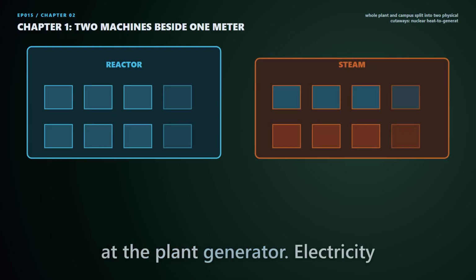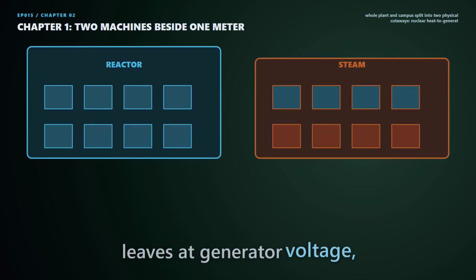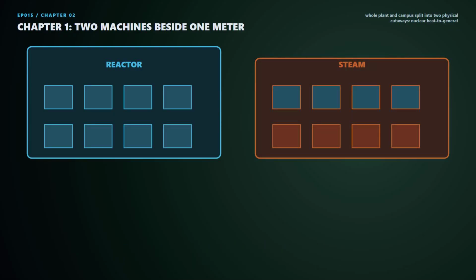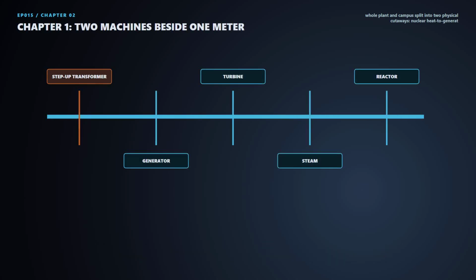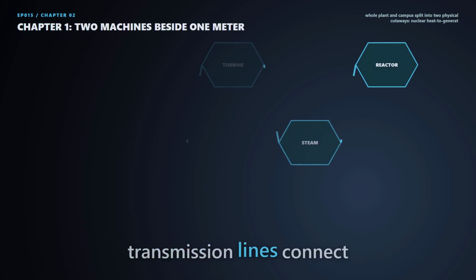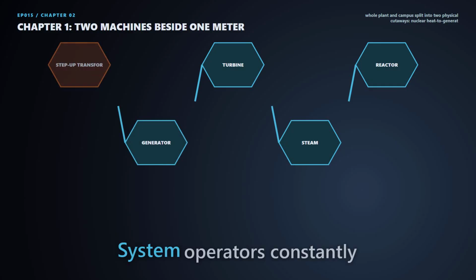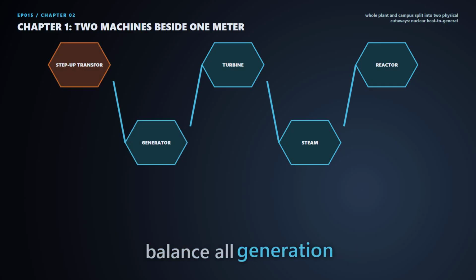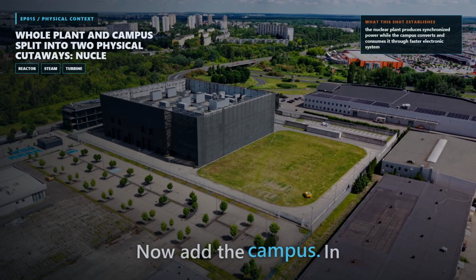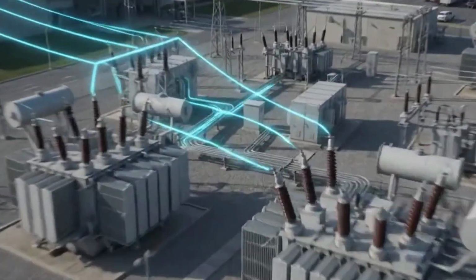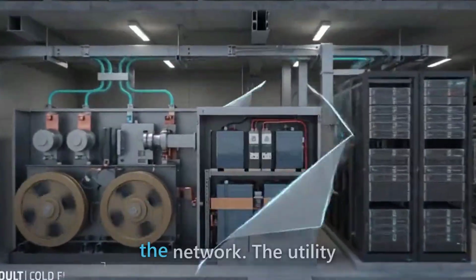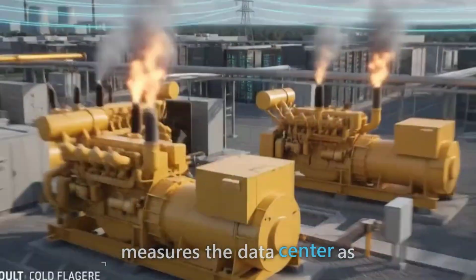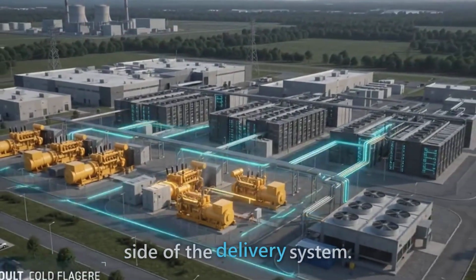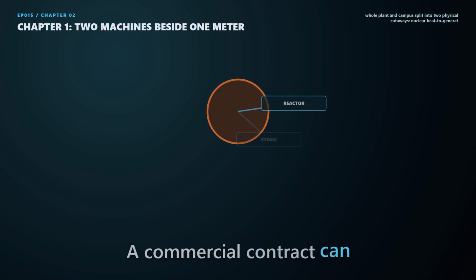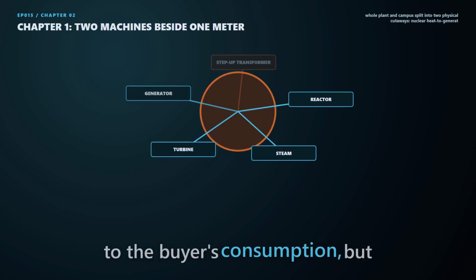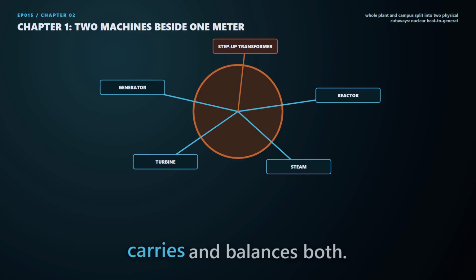Start at the plant generator. Electricity leaves at generator voltage, passes through a step-up transformer, and enters the high-voltage switchyard. From there, breakers and transmission lines connect Susquehanna to PJM. System operators constantly balance all generation and demand across the region. Now add the campus. In a traditional front-of-the-meter arrangement, the plant injects power into the network. The utility measures the data center as a retail load on the other side of the delivery system. A commercial contract can match the plant's output to the buyer's consumption, but the physical grid still carries and balances both.